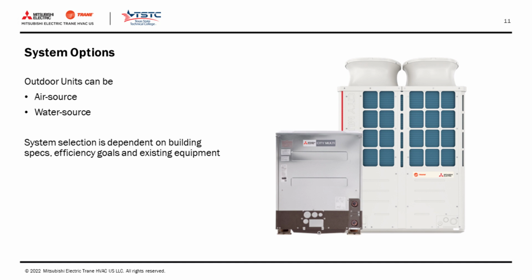Water source systems rely on chilled or heated water to regulate the refrigerant temperature year-round. Water source condensing units may be served by any water loop you like: independent cooling tower or fluid cooler, a campus water loop supply, a geothermal field, etc.